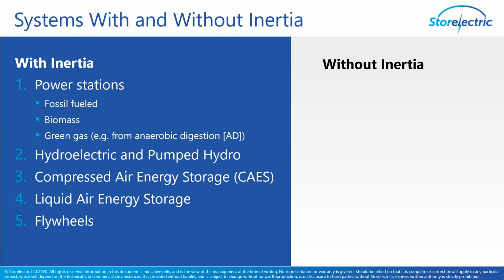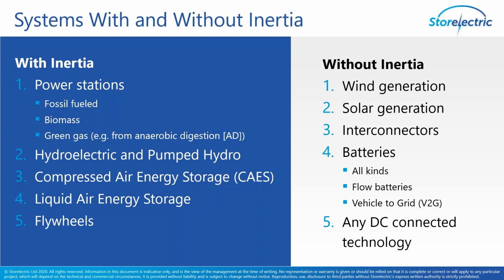Systems with inertia are anything with large rotating machines, which is power stations, hydro and pumped hydroelectric, compressed air energy storage, liquid air energy storage, and flywheels. We're going to be hearing about our compressed air energy storage and other people's flywheels, and also liquid air energy storage later on in this seminar. Without inertia, wind generation, solar generation, interconnectors have no inertia because they're DC connected, and batteries, anything that is connected with a DC link somewhere in the system has no real inertia, and they can only provide simulated inertia.